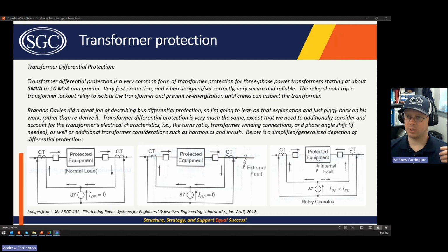So I'm going to kind of piggyback on what Brandon has already described for bus differential protection, but transformer protection also has additional considerations because the transformer has a turns ratio, so the currents aren't the same on the high side and the low side of the transformer, and there's also potentially a phase shift, and you have CTs that may be wired differently because of the transformer winding configurations. So those are things that we need to consider when we set the transformer differential protection that aren't considerations for bus differential protection. But the theory is very similar. So hopefully you'll see that once we account for those differences, it's basically the same thing.